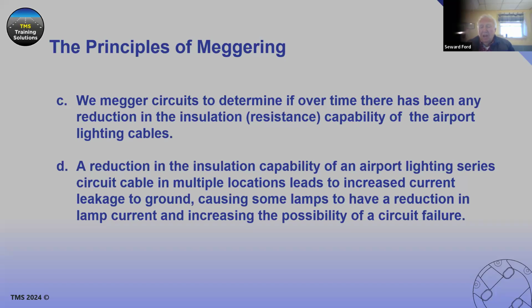A reduction in the insulation capability of an airport lighting circuit cable in multiple locations leads to increased current leakage to ground, causing some lamps to have a reduction in lamp current and increasing the possibility of a circuit failure. We can have several leakage points to ground, where those low resistance points are such that the current is more attracted to leave the conductor at that point and go to another place on that cable where it finds it less resistive, and it jumps back on the conductor at that point. So what happens in the middle? The lights in the middle are dimmed or they're out in some instances. So it's important that we don't have these multiple grounding or low resistance points to ground on the cable.